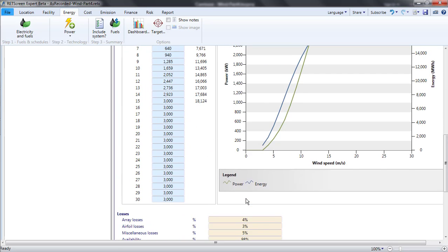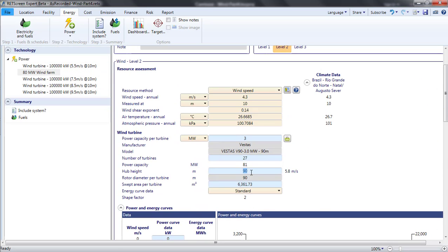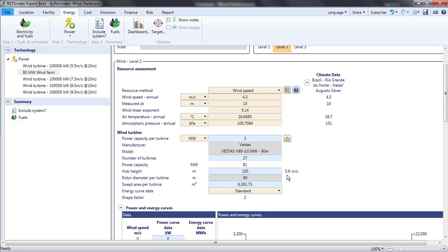If I temporarily change the hub height to 100 metres, I see that this 4.3 metres per second at 10 metre height translates to only 5.9 metres per second at 100 metres, much less than the nearly 8 metres per second from the Global Wind Atlas. This demonstrates that while sometimes the RETScreen Climate Database measurement of wind speed can yield a usable estimate for a wind farm, like at St. Lawrence, often it does not. A high resolution and accurate source of data near the hub height is essential.